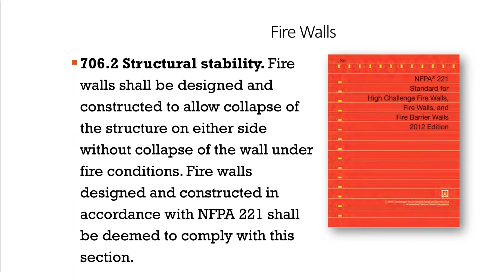So the code has brought in NFPA 221 that helps when you need a firewall between existing buildings. It's essentially using double fire barriers to create an equivalent to a single firewall. But watch how that's designed. What do you need for the double wall rating? If you're in a facility that needs a 3-hour firewall, if it were an individual wall, and wanting to use NFPA 221, the double fire barriers to achieve it, you would need 2 2-hour walls in order to have an equivalency to a single 3-hour wall.